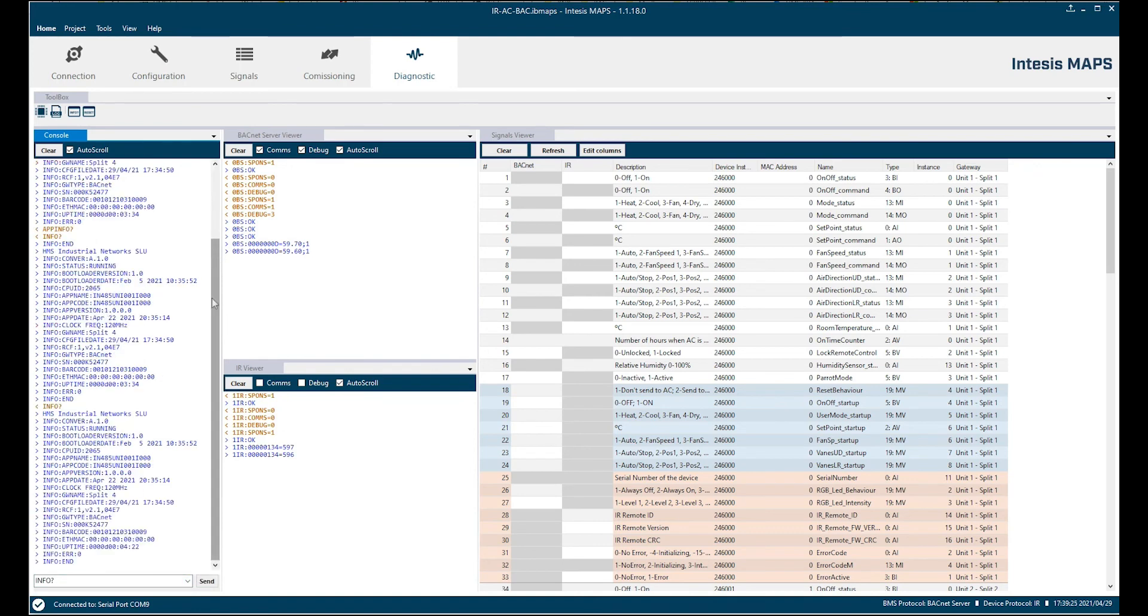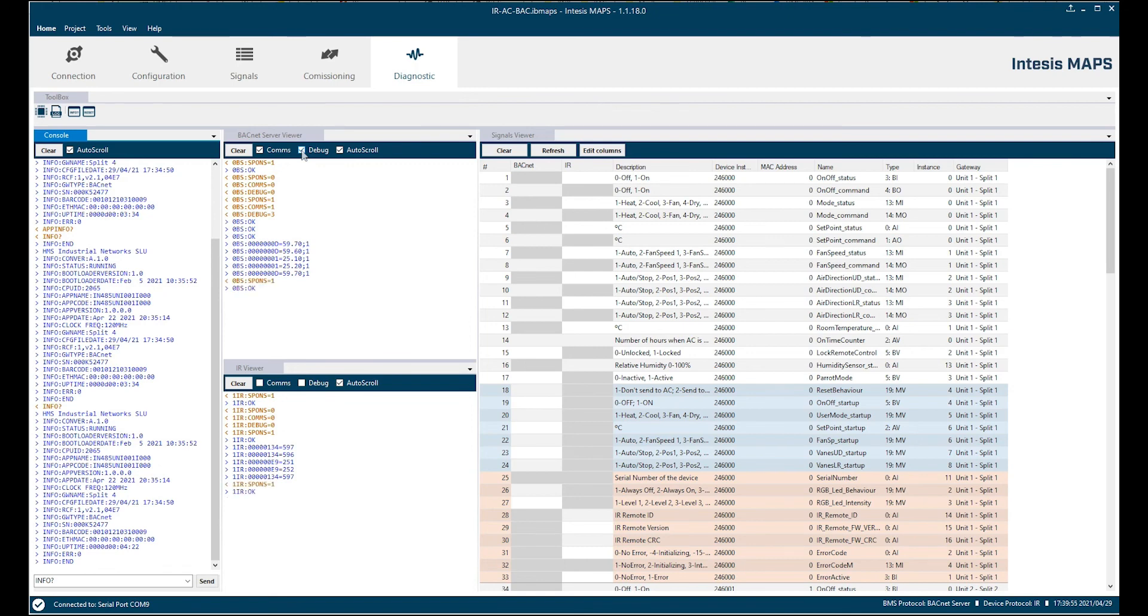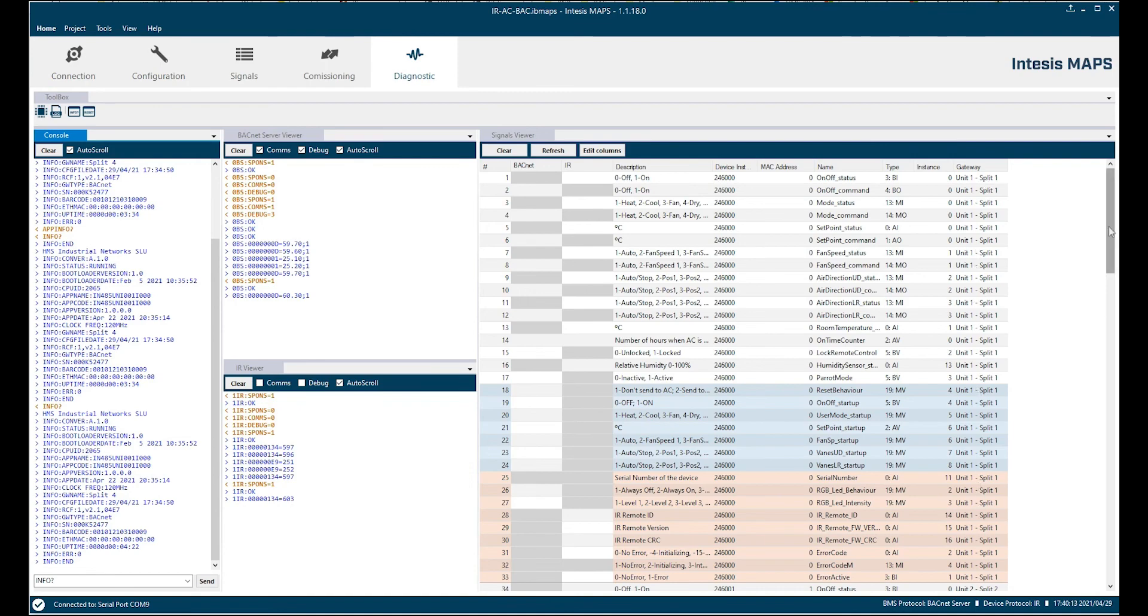Then we have two protocol viewers. The BACnet server viewer and the infrared viewer. So the BMS side and the AC unit side. And here we have three check boxes each. We can enable or disable commands. We can enable or disable debug view function. What this does is it parses some part of the information to make it more visible and easy to read. And we can enable or disable the auto scroll. So you see there are already some commands sending forth and back in our device. Remember we are connected to device 4.